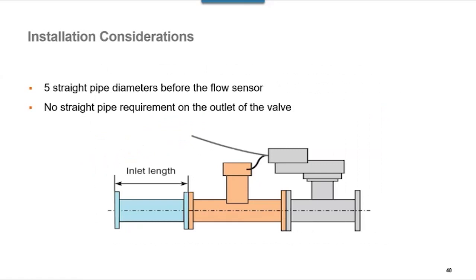Just a couple of quick things, installation considerations. For our product, you definitely need 5 straight pipe diameters before the flow sensor. No straight pipe diameters after. If you have less than 5, the valve will still function. However, you're going to see that accuracy rise quickly from plus or minus 2%. So definitely get those 5 straight pipe diameters in front of it. When you're doing verification, that's something to look out for.